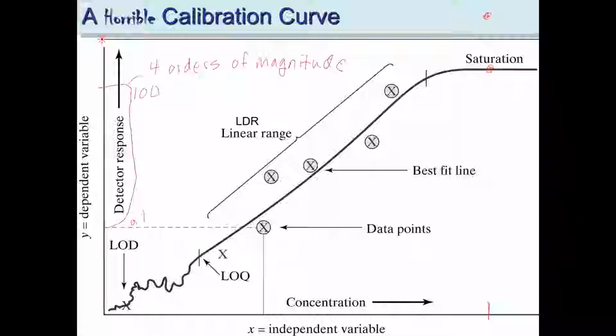And so anytime you see even a spectroscopic measurement where the peak's coming up and it starts to flatten out at the top and then it goes back down, like somebody just chopped the top of the peak off, that is saturation. It's like your detector can't see any more sample. So really strong samples will saturate your detector. And your detector, it could be a chromatograph, it could be a spectrometer. All of those instruments are going to saturate.